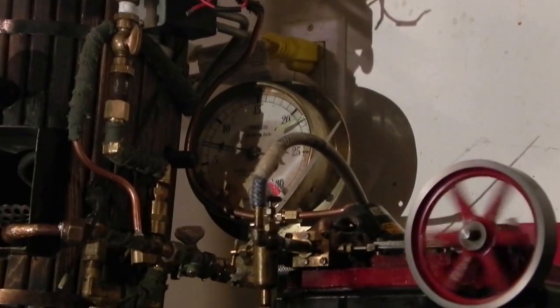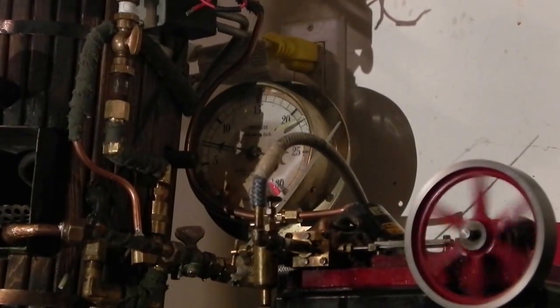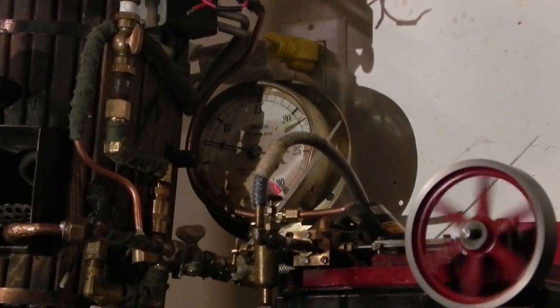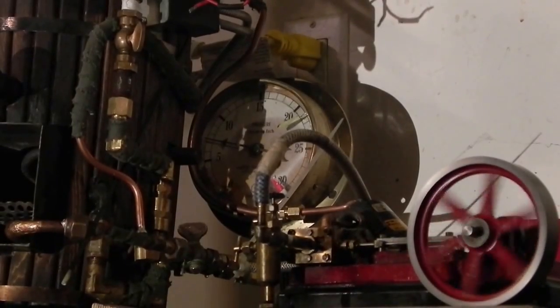We'll check the condensate afterwards and see how much oil is in it, make sure there is a displacement going on and the oil is getting into the system.